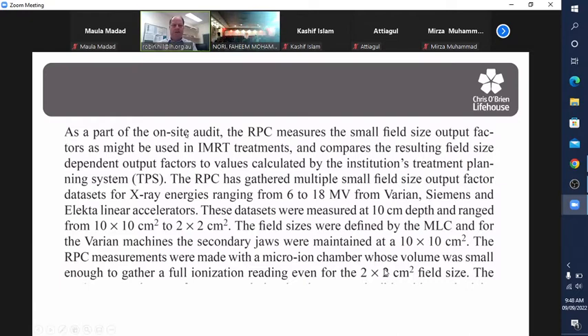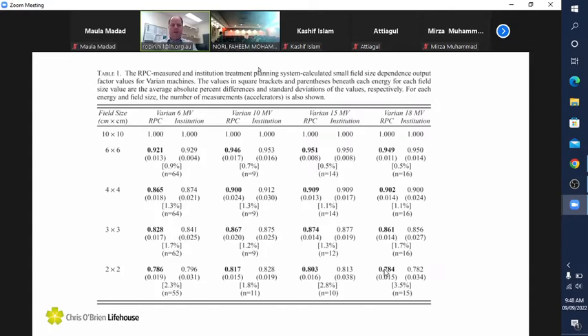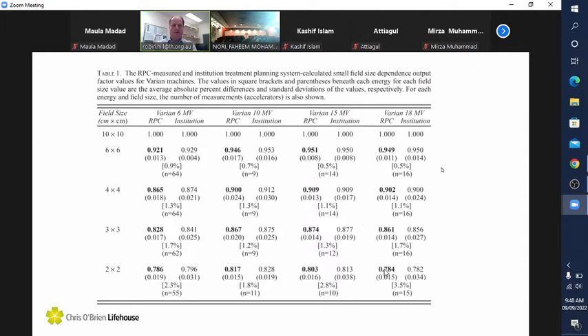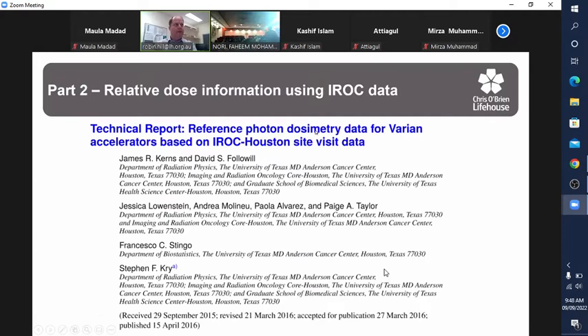And it's still a good data set. In the publication they've got data for Varian and I believe Elekta machines, and they have output factors down to two by two. This would be really quite easy to measure in an afternoon or an evening, starting with the two by two field size data. The good thing is this has been published and validated based on a lot of patients.